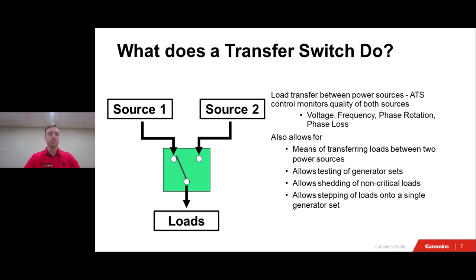This ability to transfer power between sources also allows for the means of transferring loads between two power sources, allows testing of generator sets, allows for shedding of non-critical loads, and allows stepping of loads onto a single generator. And as you can see off to those points to the right, there are a few more circumstances and situations that an automatic transfer switch can be used for.